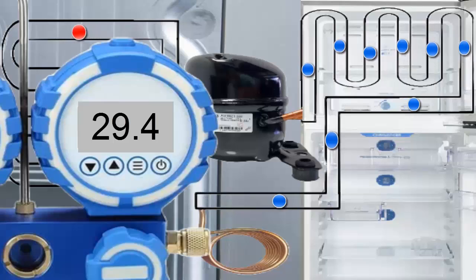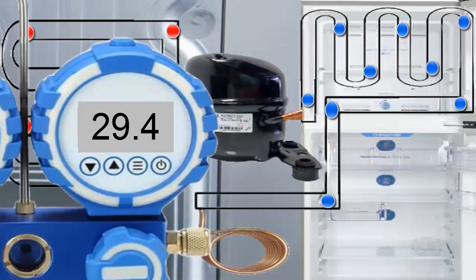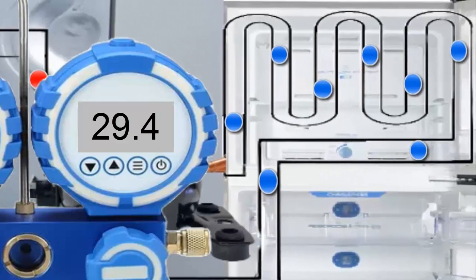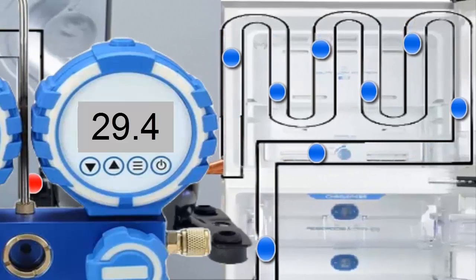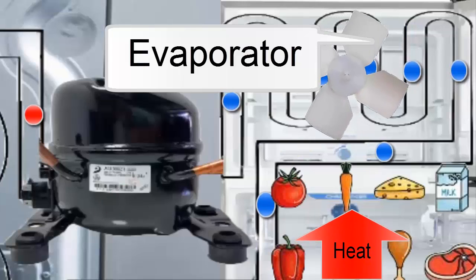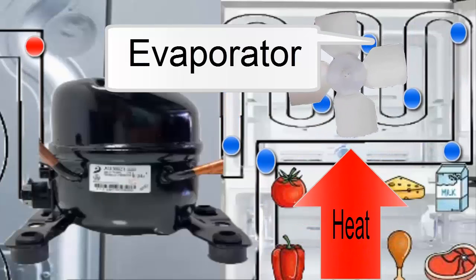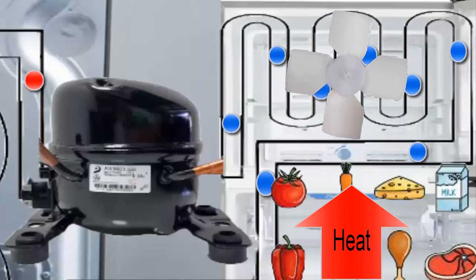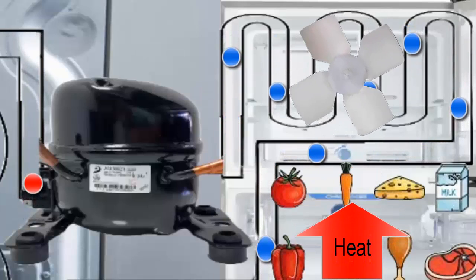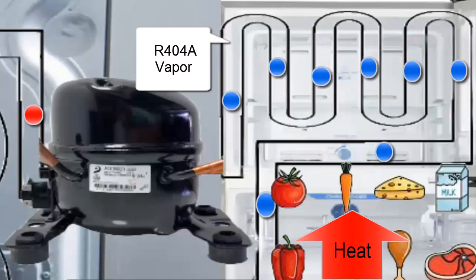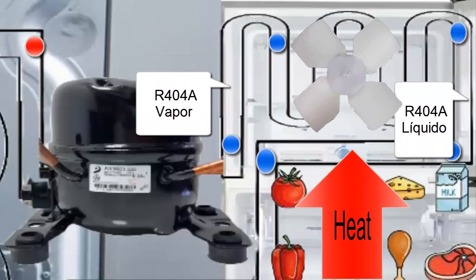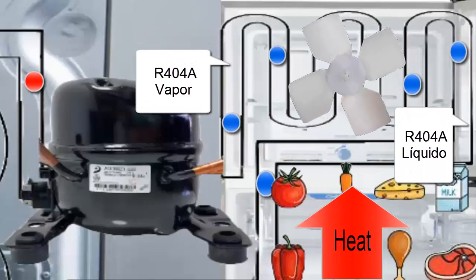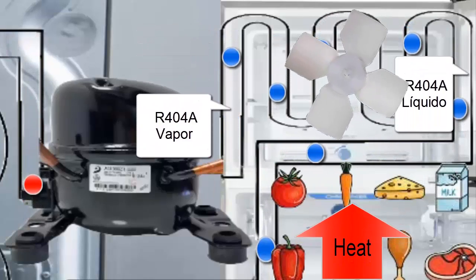The R404A refrigerant enters the evaporator in a liquid state at a pressure of 29.4 pounds per square inch. With this pressure, it is achieved that the R404A in the evaporator has a temperature of minus 20 degrees Celsius. With this low temperature and the help of the fan, the heat from the food quickly passes to the refrigerant R404A, causing it to evaporate.